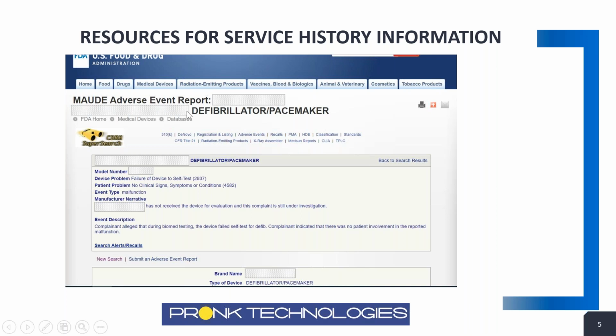So here you have a defibrillator. You can see it here. At the top, below that, you'll have information like the model number, what kind of problem it had. You can see this one in particular has a device failure. It's a self-test failed. And it will give you information about whether there was a patient related to this incident that was reported, or this report that was made. What kind of event was it? This was a malfunction. And then the manufacturer actually is required to investigate and determine what could have happened with any and all of these reports submitted to the FDA.